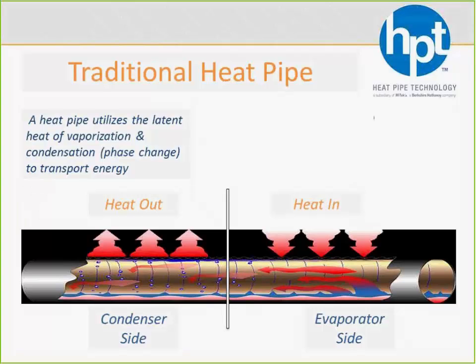So I'm sure everybody here is an expert when it comes to heat pipes, but that's not going to stop me from showing this picture and telling you how a heat pipe works. When you strip away the curtain and the black magic that surrounds the heat pipe, it's really a tube. It's got refrigerant in it, and when you apply heat to one side, that refrigerant is going to pick up the heat. It's going to boil, and when it boils, that creates a pressure differential, and that vapor is going to flash to the other end of the heat pipe, where it's now in contact with a cooler air stream, gives off that heat, condenses back to a liquid, and then that liquid goes back to the other side, into the space left by the vapor, and that cycle is just going to repeat. So it's going to pick up heat on one side and dump it to the other side. We don't need a pump or any power to make it work. All we need is that delta T. It's going to create a delta P, and you're going to get heat recovery, heat transfer from one side to the other.